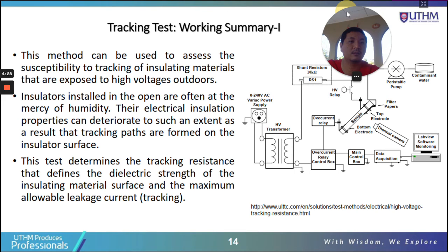All right, let's just quickly look at the summary. So this method can be used to assess the susceptibility to tracking of insulating materials that are exposed to high voltage outdoors. We want to check on the insulation because the insulation is exposed outside, exposed to the rains. So during rains, can it withstand that high voltage? Insulators installed in the open area are often at the mercy of humidity, a lot of humidity outside, so their electrical insulation properties can deteriorate to such an extent that tracking paths are formed on the insulated surface.